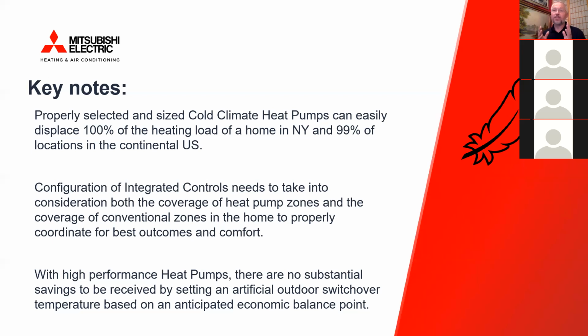But the reality is that the amount of savings that occurs is so small, and it's highly variable depending on what's going on with commodities. We've got a couple of folks from Efficiency Maine on the call right now, and they did a study on this economic balance point. At least in Maine, where, granted, electricity is cheaper than it is in New York State, for instance, or in Massachusetts, the economic balance point was around 0 degrees against an oil-fired boiler. And if you were to switch perfectly on that economic balance point, you would save some handful of dollars, $4 or $5 per year, by switching between the two. And so it's not very much.